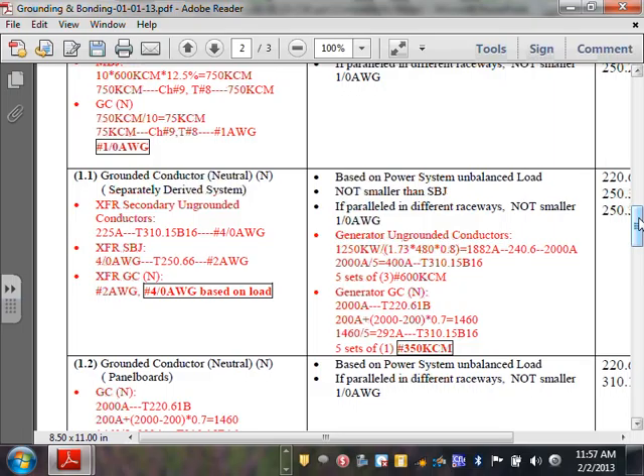My neutral conductor, guys, personally, here's what I would do. I take the first 200, remember, I leave them alone. Anything higher than 200, cut it by 0.7, came up with this, divide by 5, and that's my neutral conductor size, 350. So what's the size of the phases? The phase was 600 and my neutral 350. That's how I size my neutral conductor for the generator.